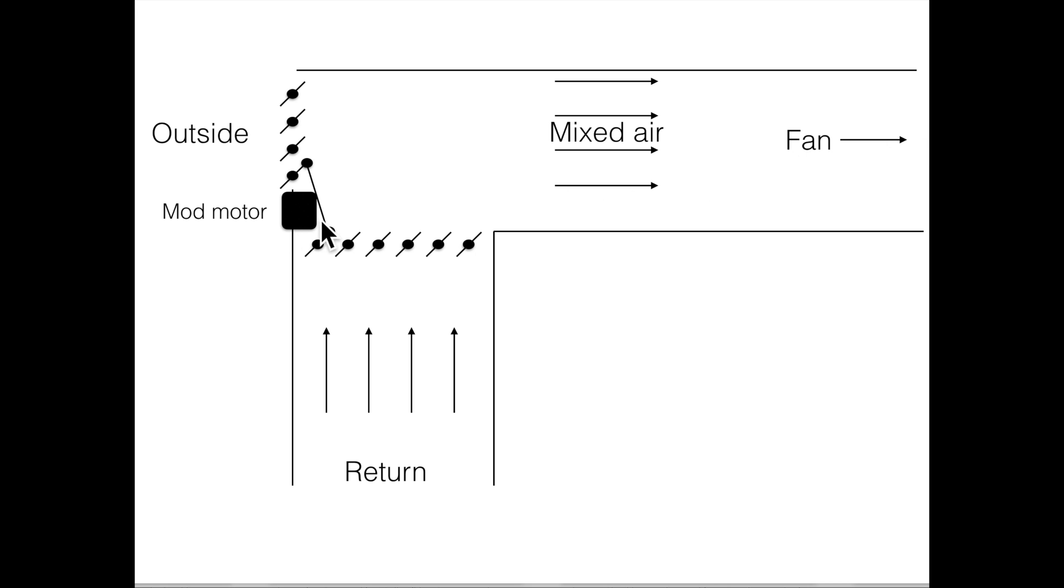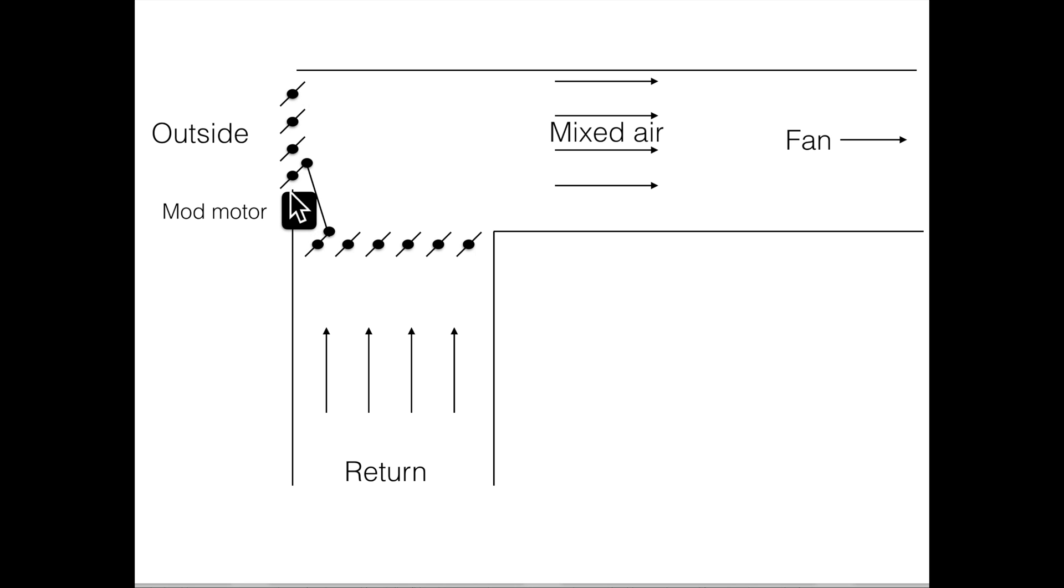Now the mod motor is going to adjust these dampers back and forth to determine how much outside air goes in with how much return. If I close these way down, most of this will be return air, and thus the mixed air temperature will go higher.